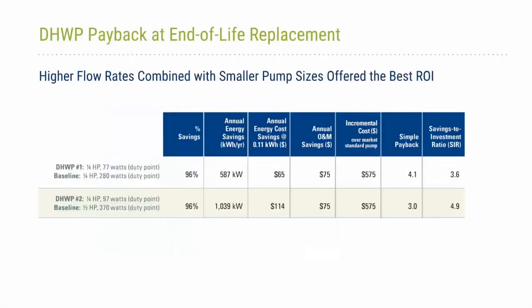Okay, next slide. So this is a table that shows you what the economics look like here. I'm just going to go through these one by one. The annual energy cost savings is a combination of the energy cost savings and the estimated demand savings. They have a complicated time of use rate here, so we did try to estimate what the demand and energy savings were. Given that they operated continuously during the middle of the day, we just assumed that the demand savings are coincident with the peak savings there.